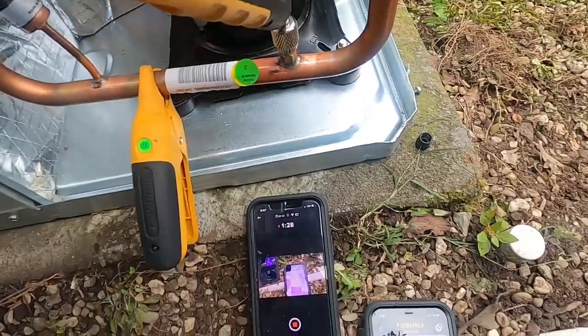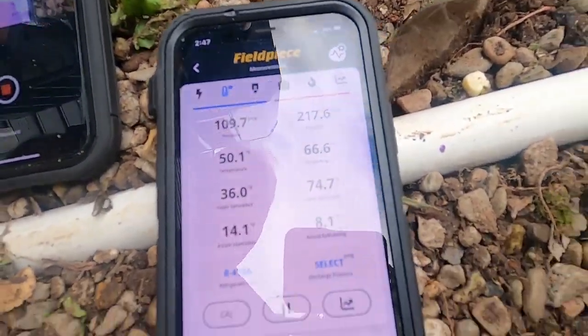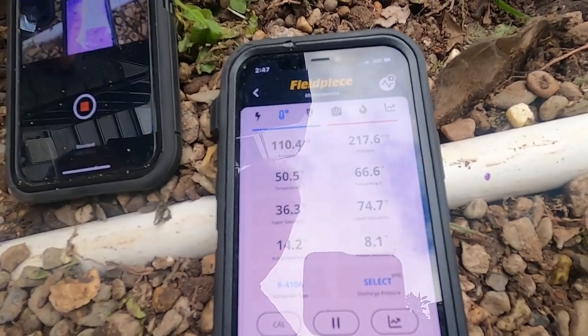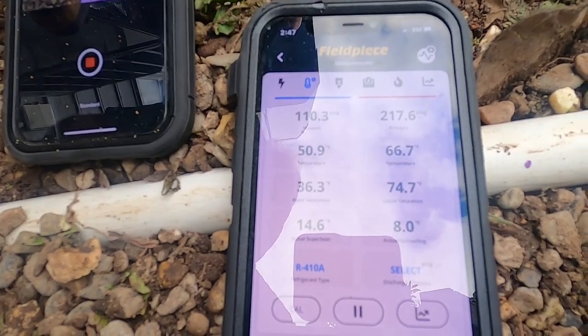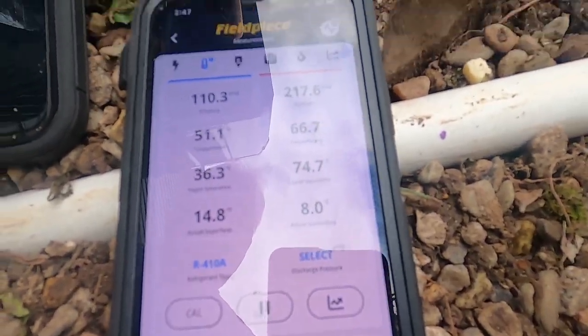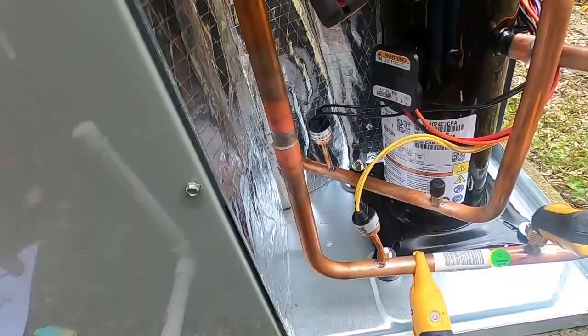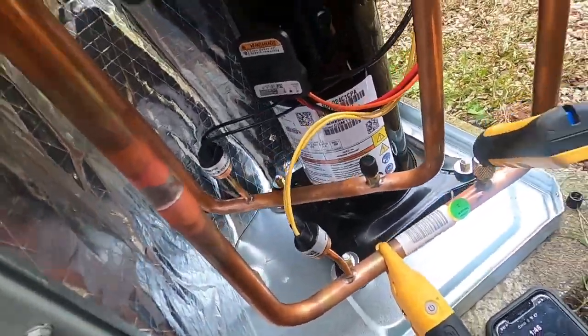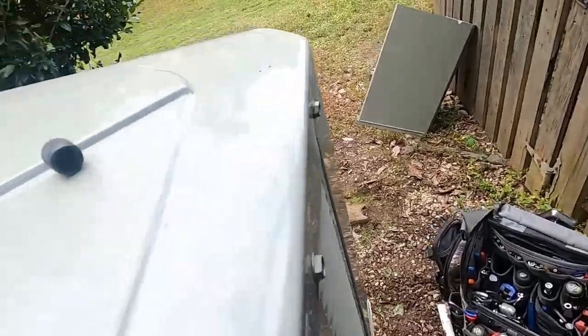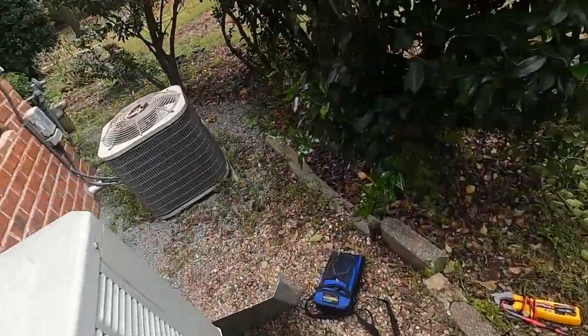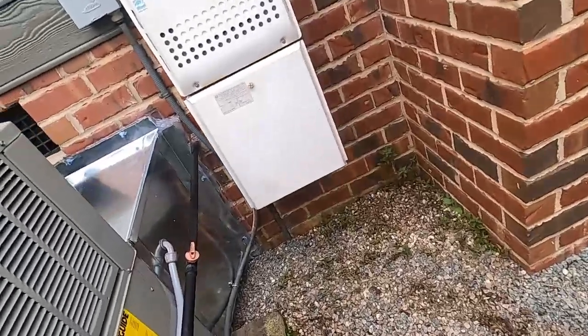It's 62 degrees outside. It's 68 degrees inside. A 109 and a 217. A 14, almost 15 degree superheat and 8 degree subcool. We're going to check our temperature split. I know it's roughly 60 whatever inside, so let's go check our supply. Check our blower performance chart with our statics.